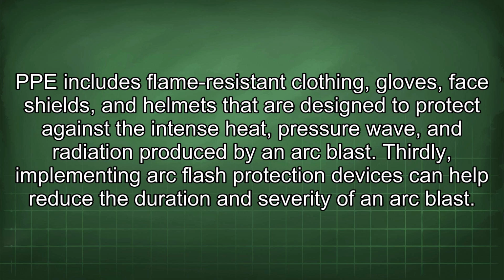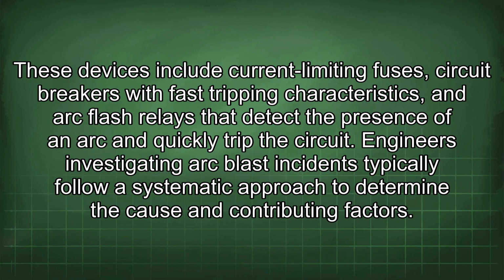Thirdly, implementing arc flash protection devices can help reduce the duration and severity of an arc blast. These devices include current-limiting fuses, circuit breakers with fast tripping characteristics, and arc flash relays that detect the presence of an arc and quickly trip the circuit.